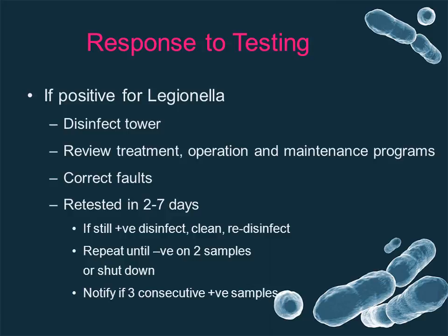If the specific test for Legionella is positive, then the tower must be disinfected and its treatment, operation and maintenance programs reviewed so that any faults can be corrected. The water must be retested 2 to 7 days later, and if it remains positive, the tower must be disinfected, cleaned and re-disinfected until 2 consecutive negative samples are returned or the tower is shut down. If in the course of testing 3 consecutive positive samples are obtained, the tower must be notified to the government department.